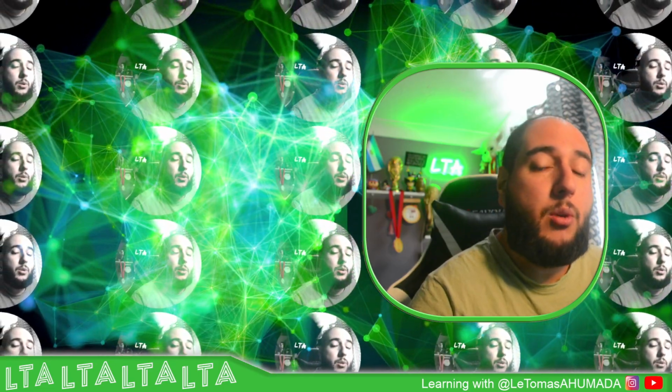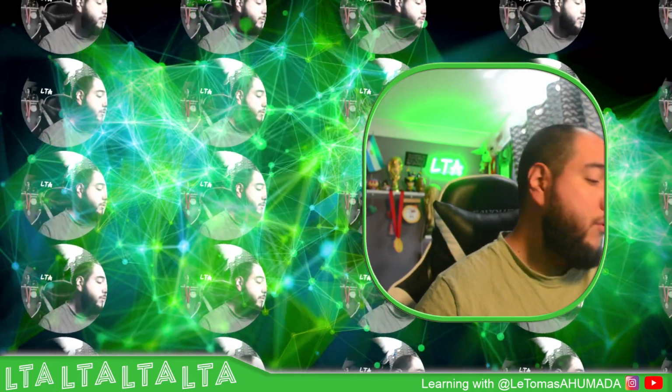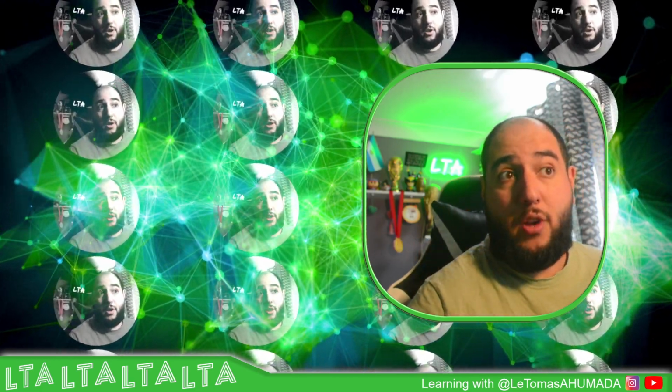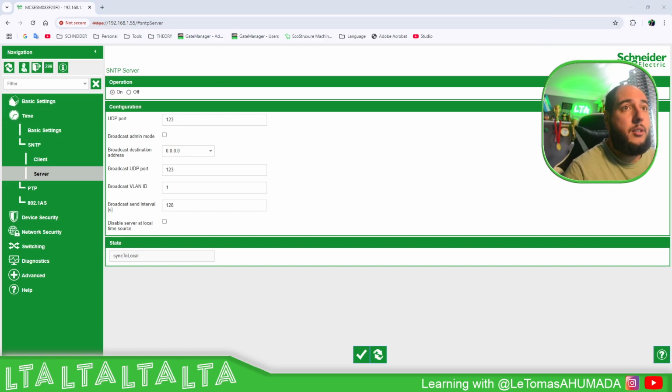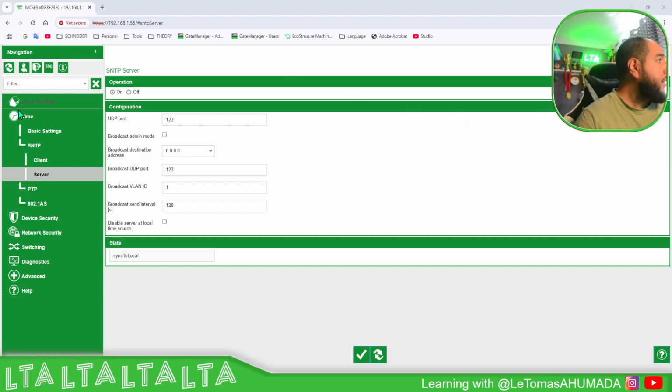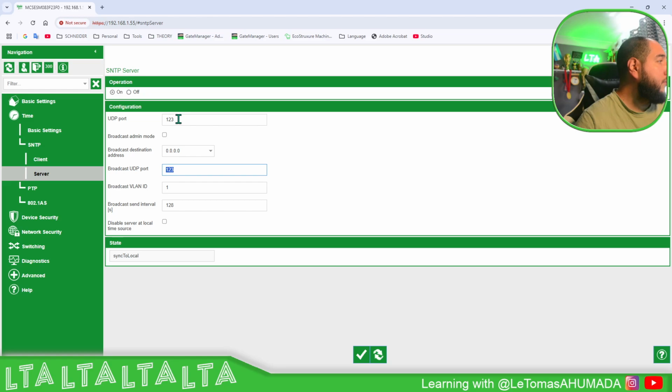I'm your host, M11, and in this video we're going to see how we can use the SNTP on the M172. So let's go first to my SNTP server. In my case I'm going to use the Modicon switch as an SNTP server. A few pieces of information that we need from here: the IP address of the server, in this case this one, and also the port that we're going to use. It's going to be 123 in my case. This is the information that we need in order to connect and see the time. This one already has a different time from my PLC.